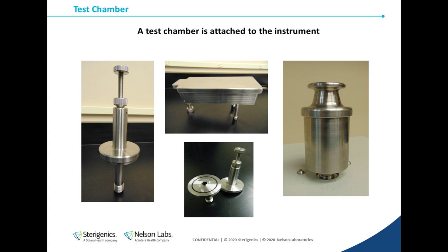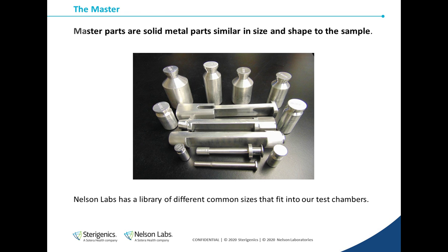The first thing is we need a chamber. The chamber is connected directly to the instrument and it holds the sample. We have a few different chambers for different sample types. Next, we need a master. The master is a solid metal part that's similar in size and shape to the test sample. Since it's a solid metal part, we know that it has no leaks.